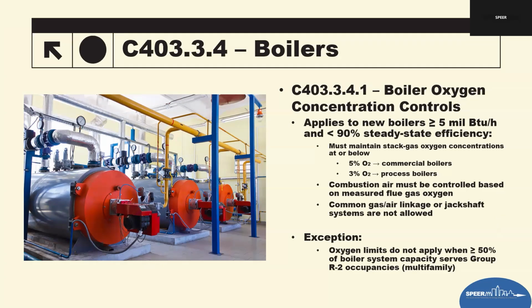These limits come directly from table 403.3.4.1. So to meet these targets, the boiler must use an O2 trim control, meaning combustion air volume is adjusted in real time based on measured flue gas oxygen. Importantly, the code prohibits old style linkage, no jack shafts or common air to gas to air linkages. So modern independent modulated systems are required.